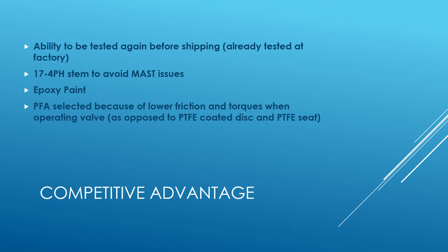While the valve is tested at the factory to API 598, we can test it again here and provide a test report showing those results. The 17-4 PH stem, while not a wetted part, helps to avoid maximum allowable stem torque issues. The epoxy paint is a corrosion-resistant coating that doesn't chip. As an improvement over our previous line, we chose PFA over PTFE for lower friction and lower torques.